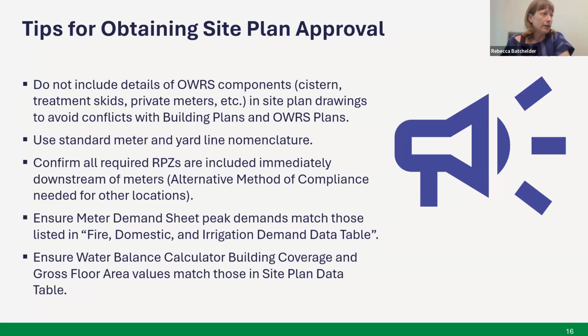I do want to see the standard meter and yard line nomenclature, which I'll highlight in the next couple slides. I'm going to confirm that all the RPZs are included immediately downstream of the meters, as mentioned before. If they're not, I need to see approval from the water protection group confirming you've checked with them and been able to place them further downstream. The meter demand sheet peak demands should match what's shown in the fire, domestic, and irrigation demand data table, another table on the Austin Water General Notes sheet listing peak demands. Those two should correspond, they're right next to each other on the sheet, so it's quick to check.